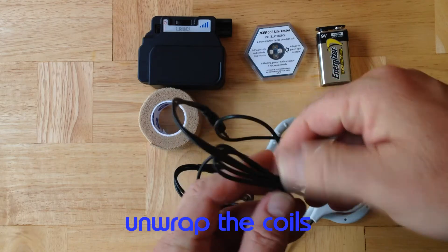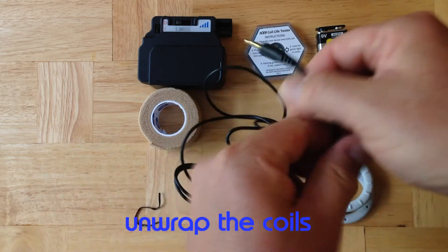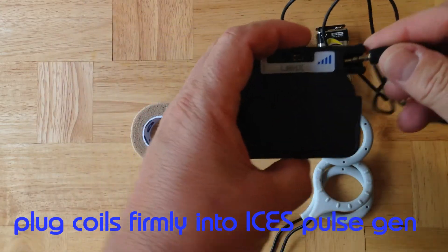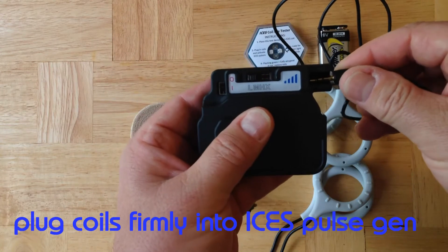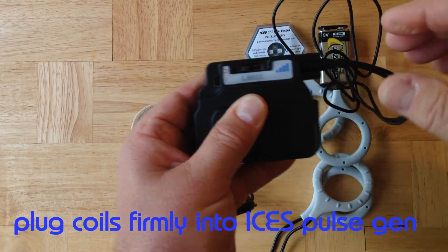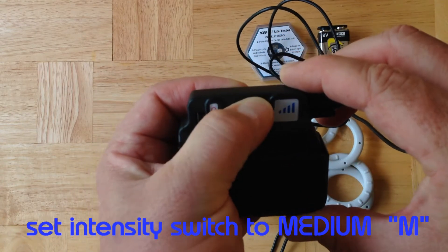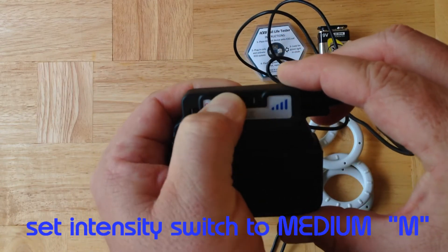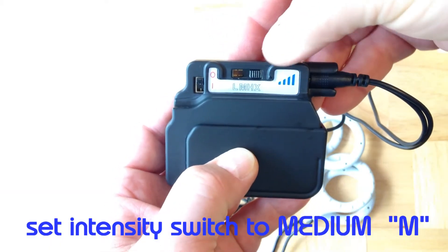Unwrap one of the sets of coils. Make sure that you stretch the coils out a little bit, and then gently plug the coils into the ICES pulse generator. This will take a second, but once you've got them inserted, put them in all the way firmly. Set the intensity switch to the letter M — this is medium. I'll increase the contrast so you can see it clearly. Also make sure that the power switch is set to zero, which is off.